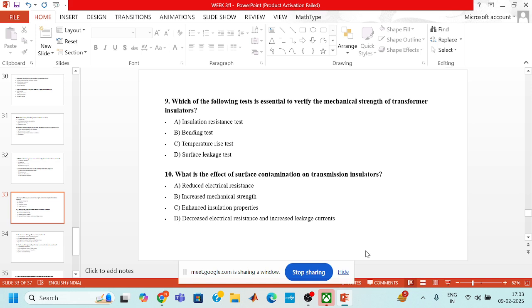Now the ninth question is, which of the following tests is essential to verify the mechanical strength of the transformer insulators? Insulation resistance test, bending test, temperature rise test, and surface leakage test. Mechanical strength, which is essential to verify the mechanical strength. Bending test. Yes, it's a bending test which is used to verify the mechanical strength of transformer insulators. Answer B, option B is correct.